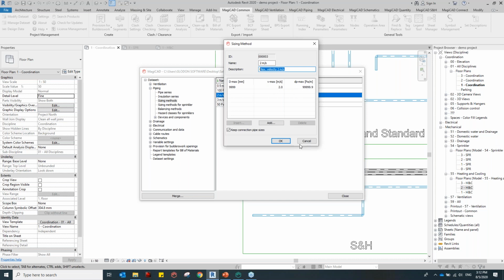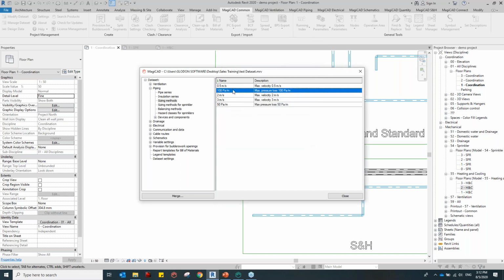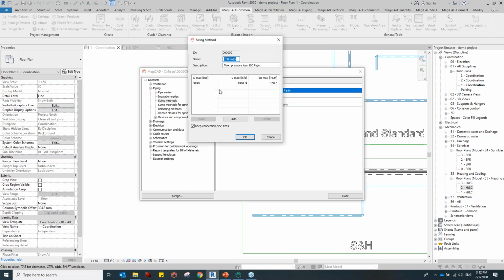In some cases you can also mix and match velocity and pressure loss. Here my maximum diameter is 999 and the velocity is 2 meters, meaning every area will follow the 2 meter per second flow rate for the pipe sizing. There's also a pressure loss method, which follows the pressure loss in the piping to do the sizing.